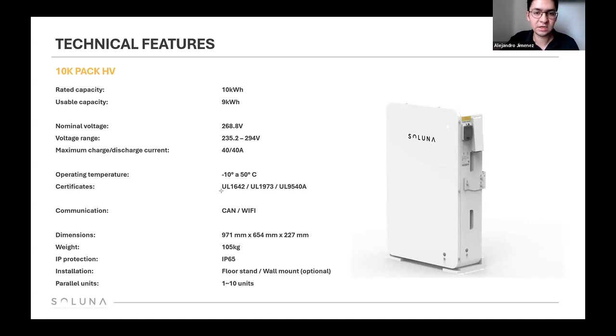The certificates: for the cell UL 1642, for the module inside the battery 1973, and for the security of the whole battery UL 9540. Communication, we have CAN protocol for the communication with the inverter. It is a single Ethernet cable, RJ45, and for the monitoring, you can use the Wi-Fi.